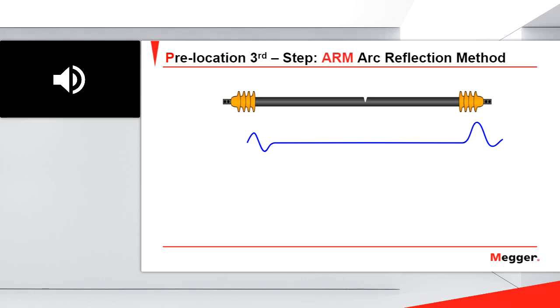Okay, now I charge the capacitor in my thumper and I release a high voltage pulse of 5 kV. When the high voltage pulse arrives at the fault, flashover happens. We will have a flashover, an arc, and this flashover will be active for a few milliseconds. A few milliseconds is how long the arc will be active, but that time will be good enough for when the second pulse of the TDR arrives.